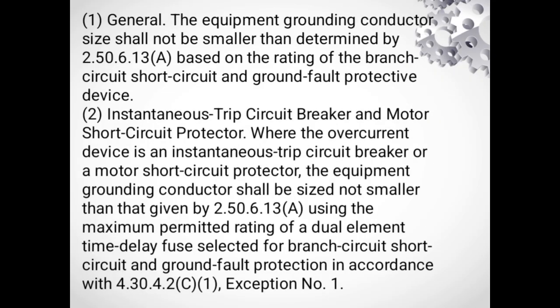D. Motor circuit. Equipment grounding conductors for motor circuits shall be sized in accordance with D1 or D2. 1. General. The equipment grounding conductor shall not be smaller than determined by 2.50.6.13a based on the rating of the branch circuit short circuit and ground fault protective device. 2. Instantaneous trip circuit breaker and motor short circuit protector. Where the overcurrent device is an instantaneous trip circuit breaker or motor short circuit protector, the equipment grounding conductor shall be sized not smaller than that given by 2.50.6.13a using the maximum permitted rating of a dual element time delay fuse selected for branch circuit, short circuit, and ground fault protection in accordance with 4.30.4.2 C1. Exception number 1.